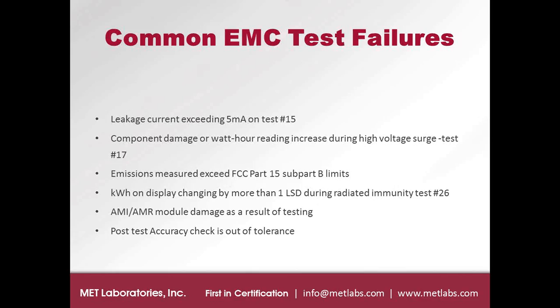Another failure is emissions measured exceeding FCC Part 15 subpart B limits. As a part of the ANSI test suite, we are required to test a minimum of 3 samples for conducted and radiated emissions, according to FCC Part 15. But the test setup is different for ANSI. Instead of a regular setup, we are required to have a specific length of the cables exposed on the tables, and the product is powered via LISNs that are also situated within the chamber. So emissions is one of the things that we see fail a lot in the lab.